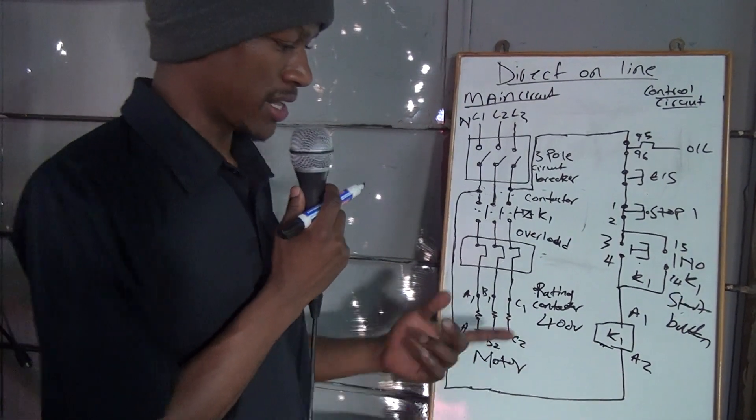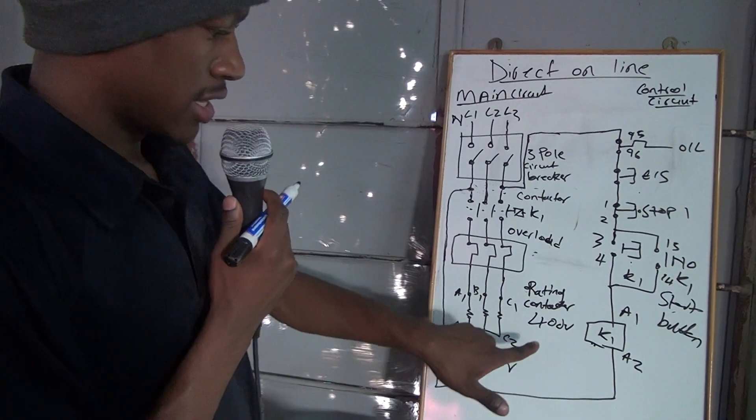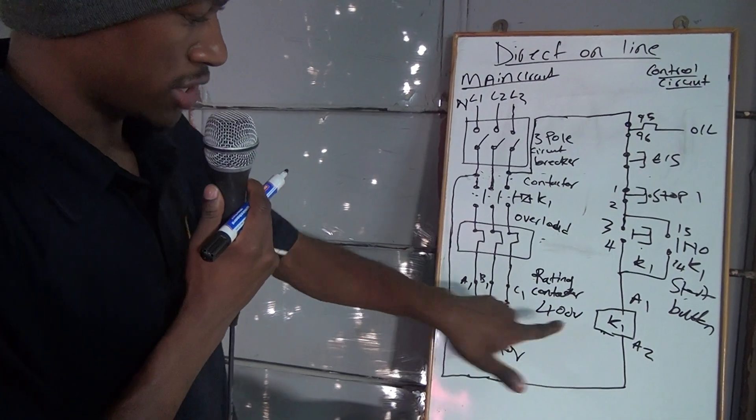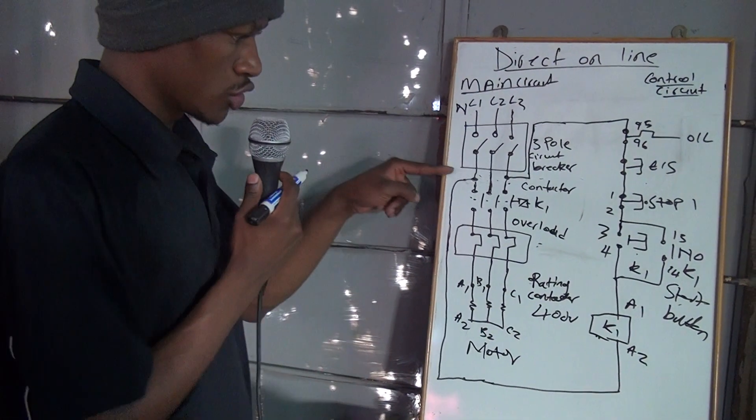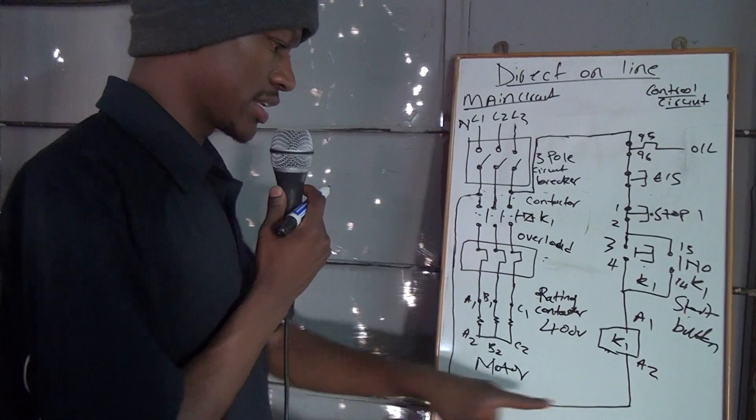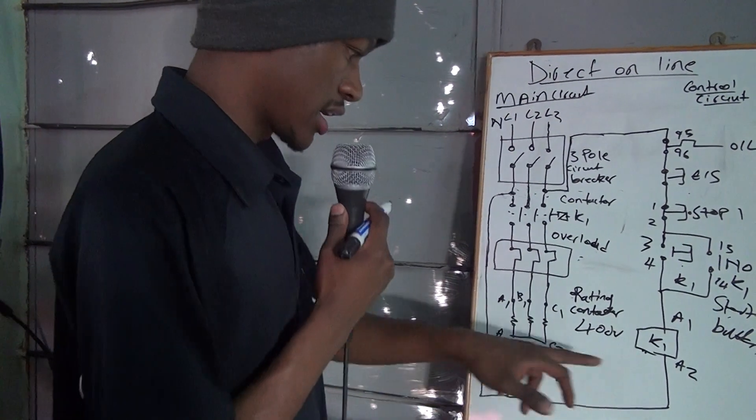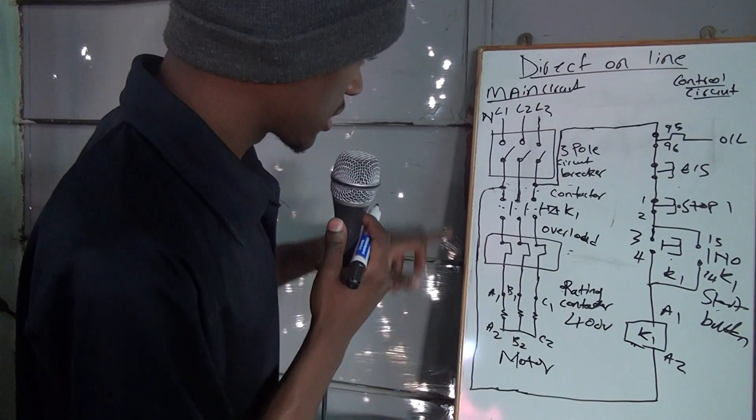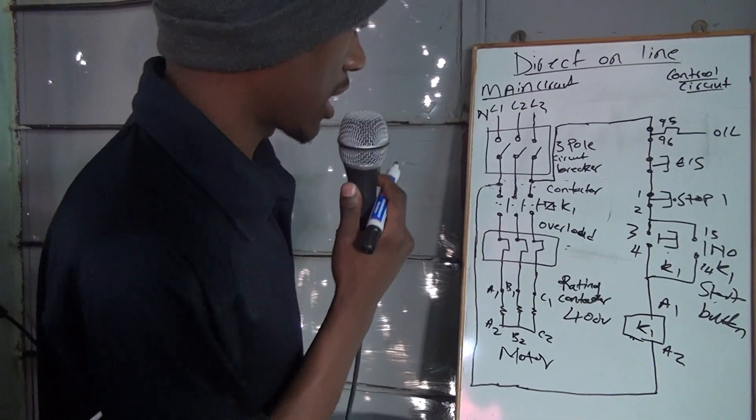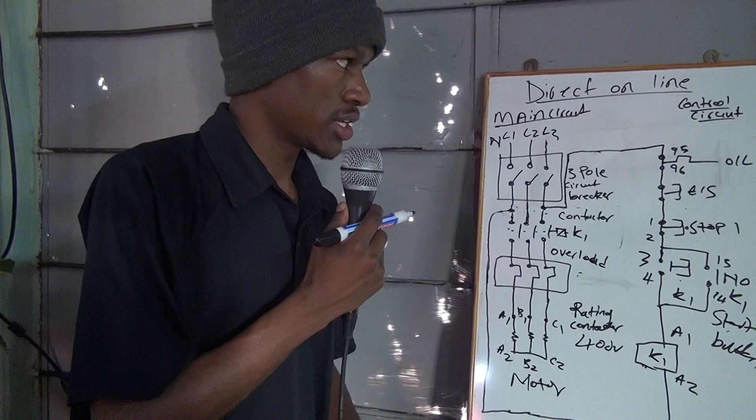And that's it. The most important part is just to understand that when the rating of the contactor is 400 volts upwards, that's when you connect on one of the lines, your A2. But if it's 220 volts, that's when you connect it to the neutral.